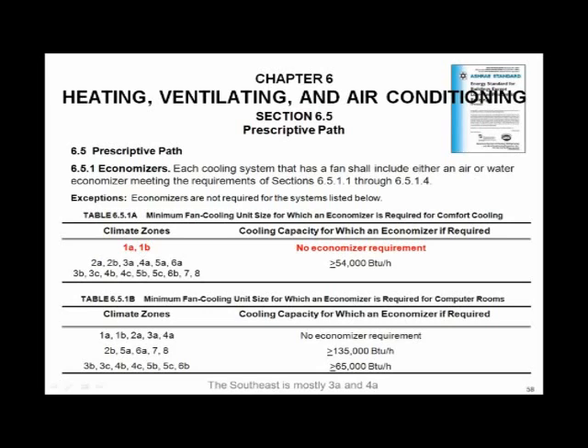Well, if you read this statement pretty quick, it says the only exemptions I see would be climate zones 1A, climate zones 1B, no economizer required, or if your loads are smaller than 54,000 BTUs. 54,000 BTUs is what, about 4.5 tons? That's pretty small. So where would this exemption, 1A and 1B climate zones, be? Do you have to do an economizer where you live in the country? That's the question. Let's take a quick look and see what these climate zones are all about.